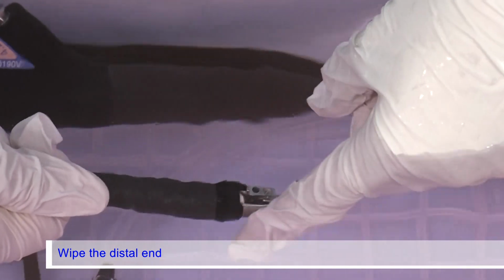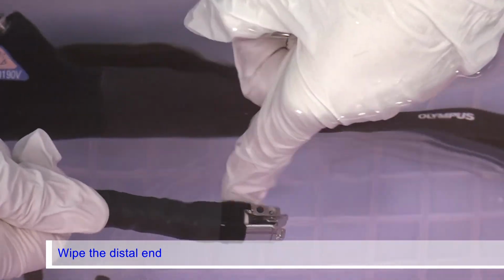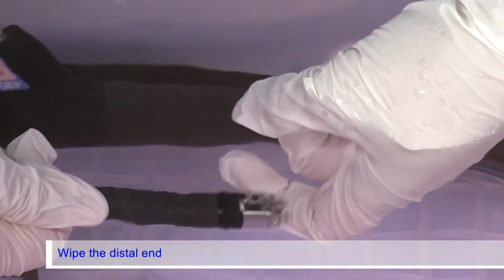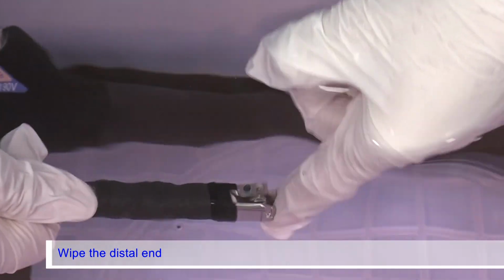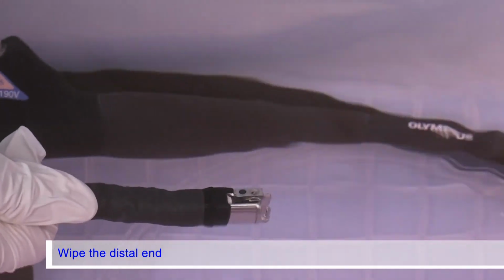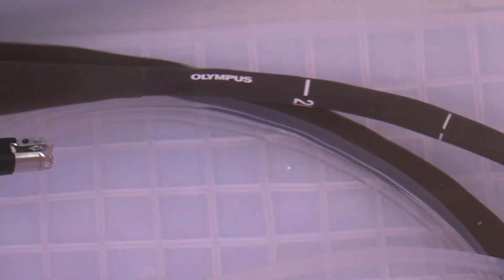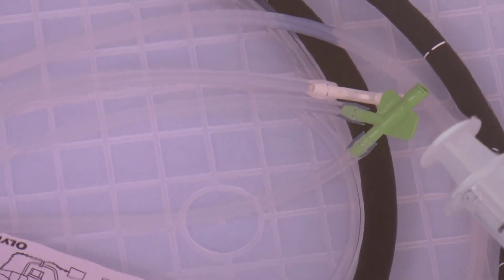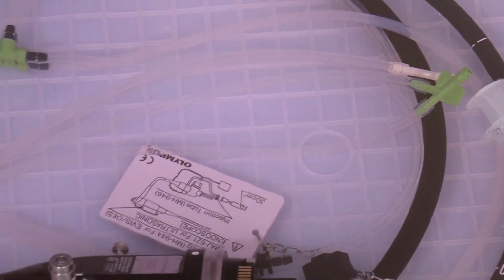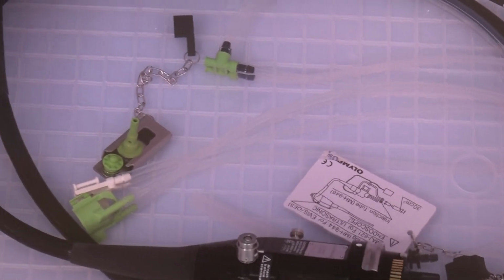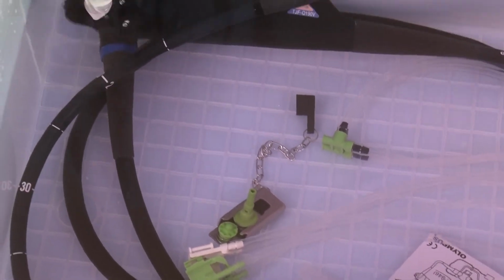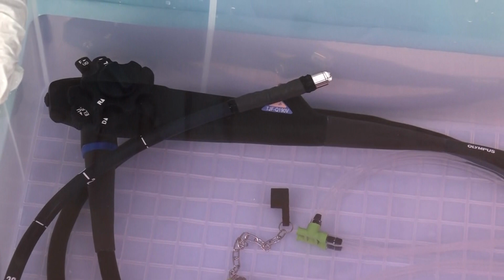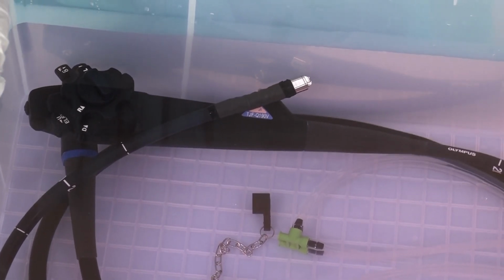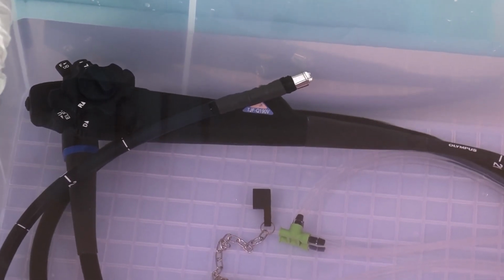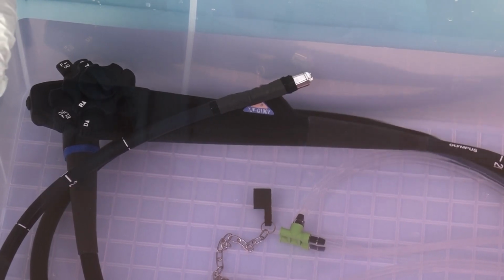While immersing the endoscope completely in the disinfectant solution, wipe the distal end of the endoscope to remove air bubbles using your gloved fingertips. Confirm that there are no air bubbles on the surfaces of the endoscope and accessories. If air bubbles adhere to the surfaces while immersing the endoscope completely in the disinfectant solution, remove them using your gloved fingertips, clean lint-free cloths, or a clean 30 milliliter syringe.